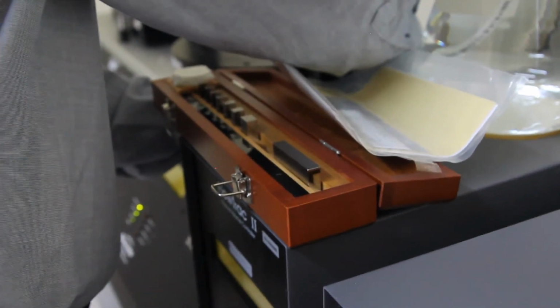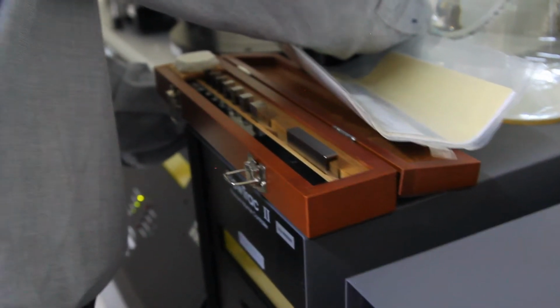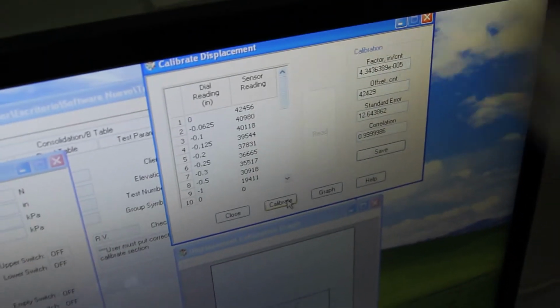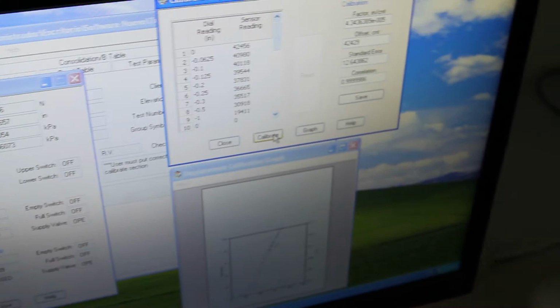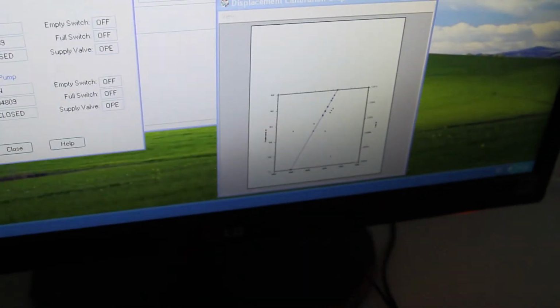I got my 8th point and my last point, which is 1 inch. So my calibration is done. I got all my points in. I got my calibration factor, I got my standard error, my correlation, this is the graph, and in order for this new calibration to take place, I just have to hit save.